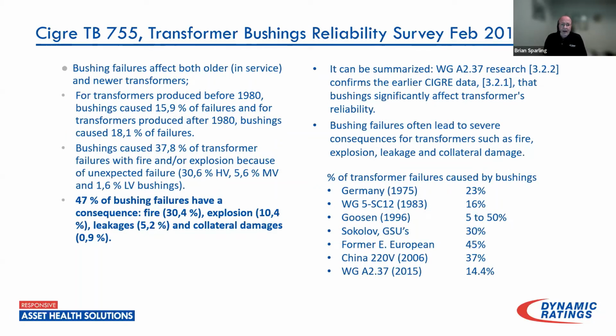So CIGRE, which is a worldwide body of experts dealing with equipment above 1,000 volts around the world, went through what we call the Bushing Reliability Survey. It was published in February 2019. Basically, the members of the working group contributed their data on bushing failures. And it was found that for transformers before 1980, the bushings were a cause of 15.9% of all transformer failures. The other side of the coin is that when bushings do fail unexpectedly and catastrophically, the coincidence of a fire is like 30%. It does take the transformer with it when these bushings fail unexpectedly.